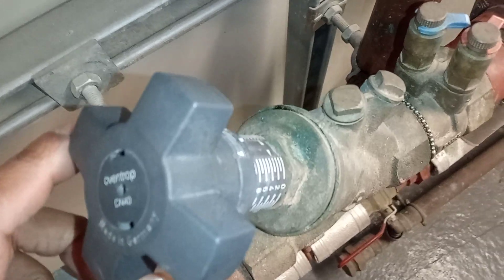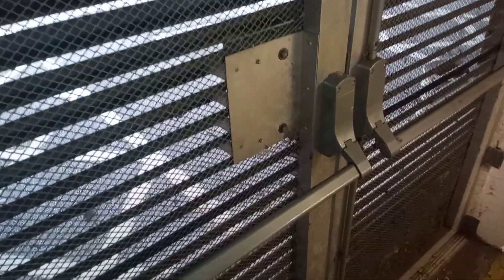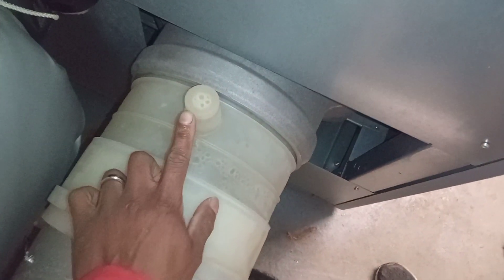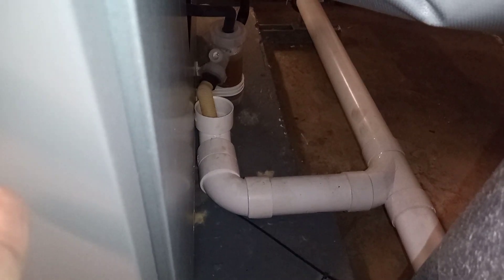There's a commissioning valve, and then some ventilation — low ventilation and high ventilation, both present. We've got our flue sample point here for our Ideal Icos EL470, a bleed point on the heating return to one of our boilers, and a condensate trap to one of our boilers down there.